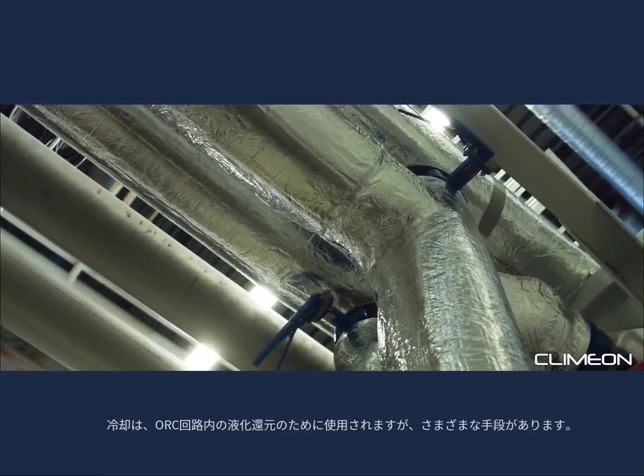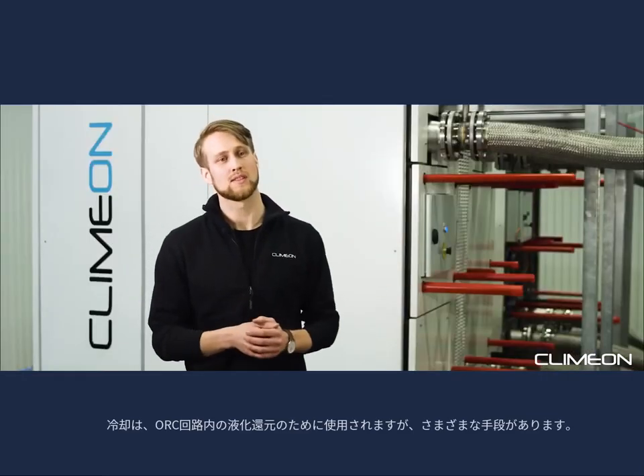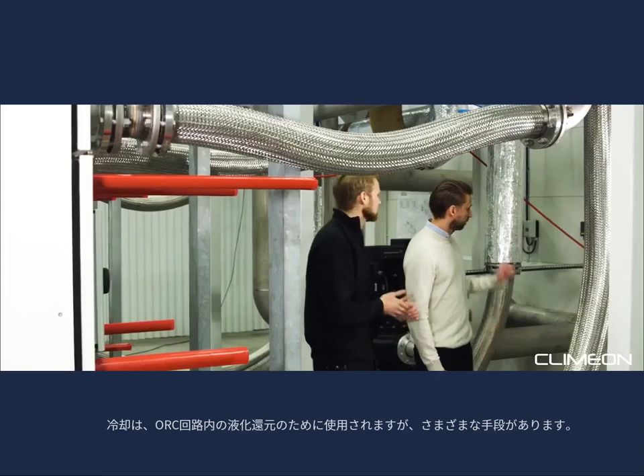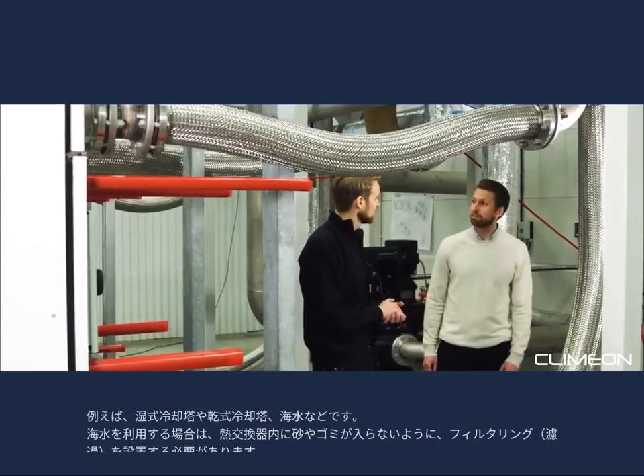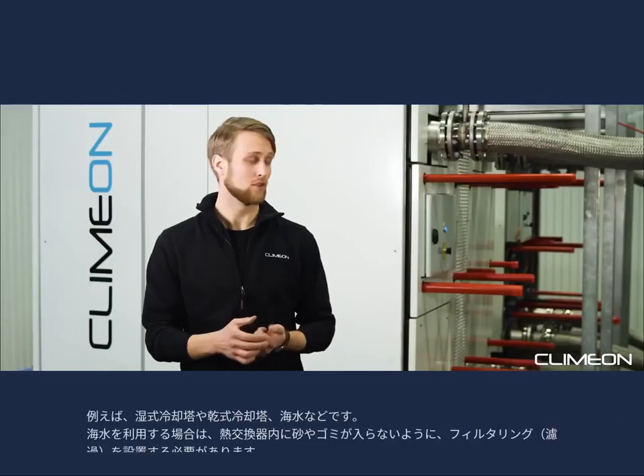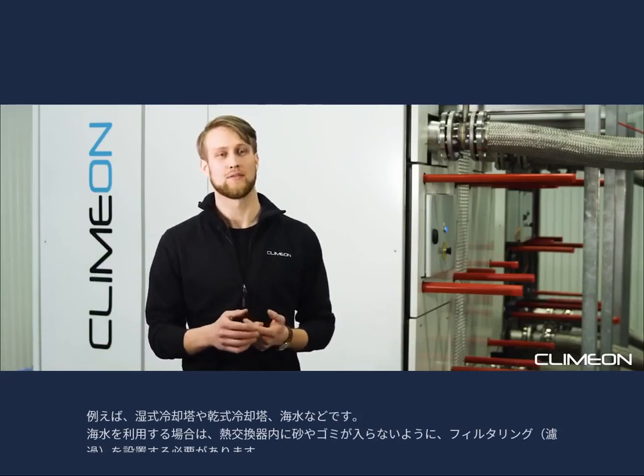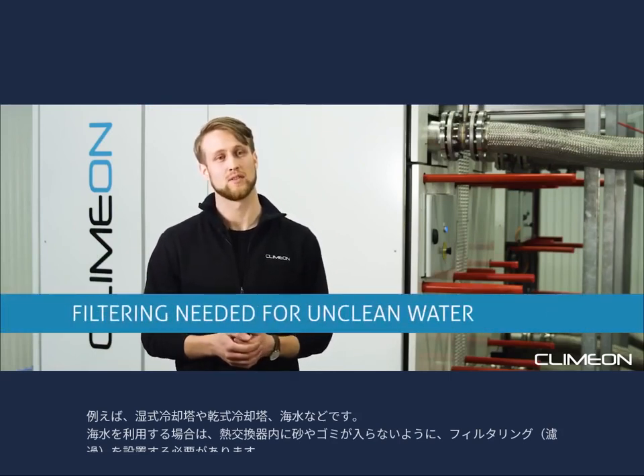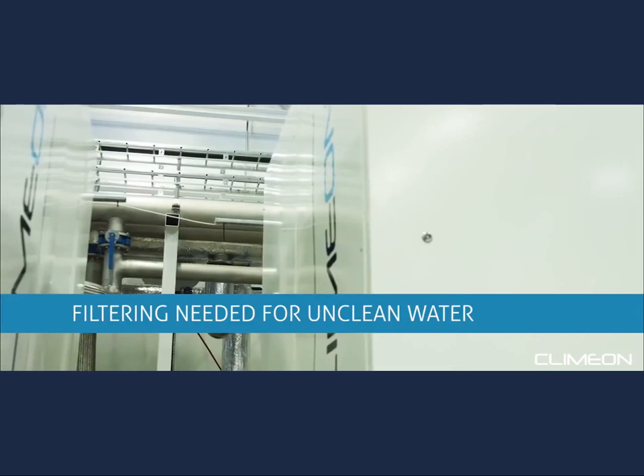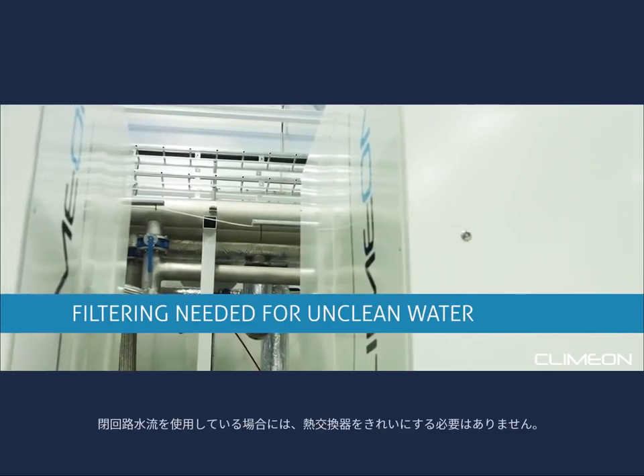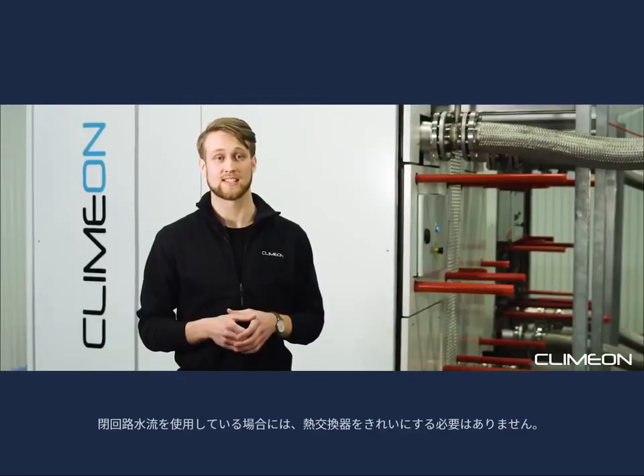Cooling is used for condensation within the unit, and you can use different sources for this cooling. It could be wet or dry cooling tower, seawater or similar. If you utilize seawater, you need to think of filtering so that you don't get debris into the heat exchanger. In case you are using a closed circuit water stream, you would not need to clean the heat exchangers.